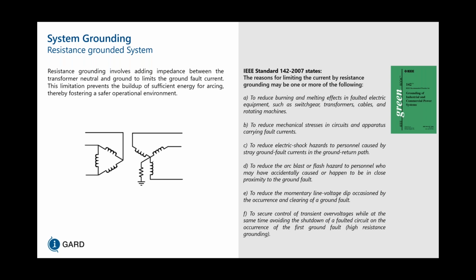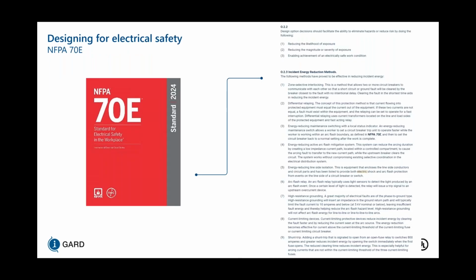In addition to that, it is to reduce the momentary line-voltage dip occasioned by the occurrence and clearing of a ground fault, which is a main issue for ungrounded systems in the case of how they experience transient overvoltages when a fault occurs. It's also to secure control of transient overvoltages, similar to the ones we see in ungrounded systems, by placing this resistor in parallel with the capacitance that exists between the conductors and ground. Now, if we size that resistor in accordance with the capacitance in the system, then we can essentially control these transient overvoltages such that we won't have the same situation as we would in an ungrounded system.